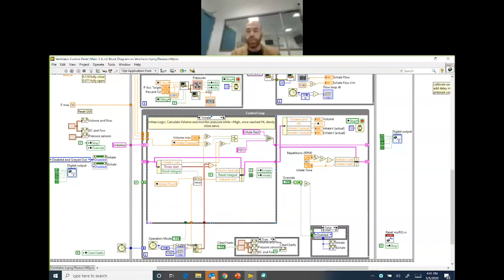If you have only one pressure sensor and one flow sensor, you can only detect either the inhale or the exhale. We'll be able to compare both of them, so we can give more information to the healthcare provider so he can also analyze and note whether there is a problem, whether it's a physical problem with the patient or whether it is a problem with the tubes, or the intubation is not correct, it is leaking, and so forth. So this is regarding the safety from the mechanical and electronic perspective.